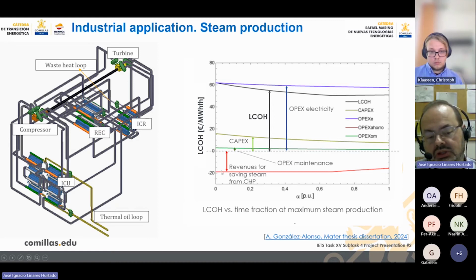This minus 20 is the revenue from the extra steam from the CHP, because we are avoiding the bleed of the steam. So the electricity produced by this extra steam produces this negative cost, that is a revenue. This is the cost of the maintenance, very low. This line is zero. This is the investment, the capex, and this is the cost of the electricity consumed, which is partially offset by this revenue. In summary, we obtain this levelized cost of heating, including capex and operation cost, which runs between 60 and 50, more or less, euros per thermal megawatt hour.